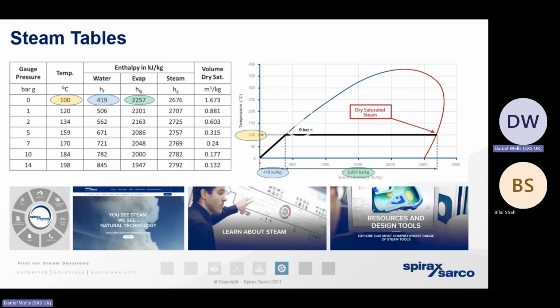At 0 bar gauge, water boils at 100 when it contains exactly 419 kilojoules of energy. Any more than that, and it starts to evaporate and boil off and produce steam. But we're only going to get dry saturated steam, which is the value shown in the steam tables, when we've added 100% of the energy in this column to 100% of the energy shown in that column. That's when the steam tables are 100% accurate. Now, in reality, poor boiler control and poor working practice in how the steam's moved means that the steam could exist in what we call the wet steam zone here.